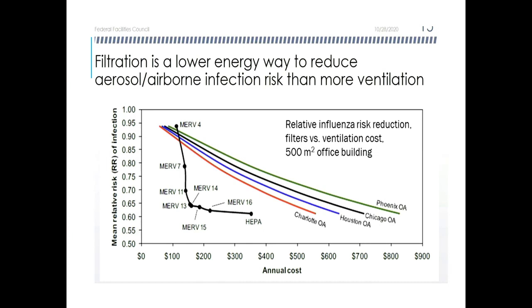This slide I stole from an ASHRAE presentation, full disclosure. But what it shows is how you can reduce risk of infection by increasing filtration efficiency and/or by bringing in more outdoor air. If you look at the little black squiggle, it shows that going to MERV 13 is far and away the biggest bang for your buck. Even going to HEPA filters doesn't give you a huge benefit, and it has a huge energy penalty. Similarly, if you look at ventilating instead of filtering, you can get to those same risk levels, but it's at a pretty significant cost because all that outdoor air has to be conditioned. So I don't think in general that this is an either or. It should be a both and, but that just gives you an idea of the relative costs there.